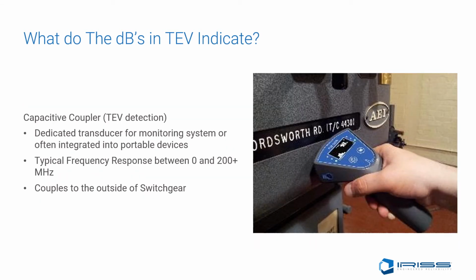Transient Earth Voltages, better known as TEV, were first discovered in the 1970s by Dr. John Reeves, who established that TEV signals are directly proportional to the condition of the insulation for all switchgear of the same type measured at the same point. TEV readings are measured in decibel microvolts.